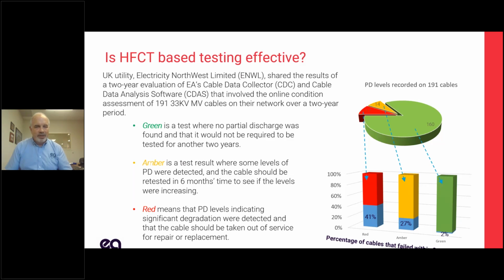And so what did they do? They left it. Within 2 years, 41% of the cables that were classified in the red failed. 27% of the cables that were in the yellow failed. Less than 2% of the cables that were in the green failed. So we can see that if I had just addressed the red cables, I'd be better off. If I addressed the red and the yellow cables, I would have had a much smaller cable failure rate over those 2 years. So yes, it is effective. This is real world data.